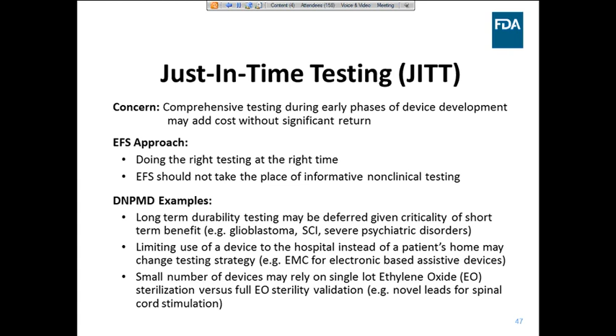You could also limit the use of your device to a controlled setting, such as a hospital or clinic, instead of allowing the patient to take the device home in an early feasibility. This could change testing strategy for electromagnetic compatibility for certain electronic-based assistive devices. For a small number of devices, you may rely on single-lot ethylene oxide sterilization versus a full sterility validation. So this may be applicable for a novel spinal cord stimulation lead.